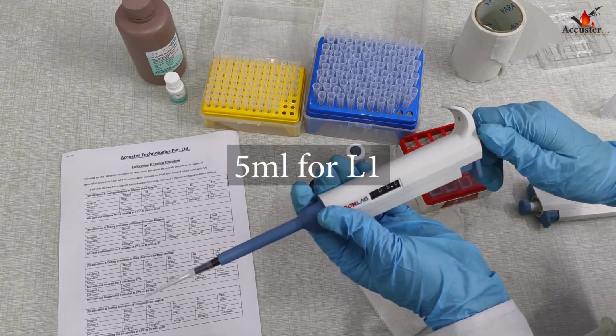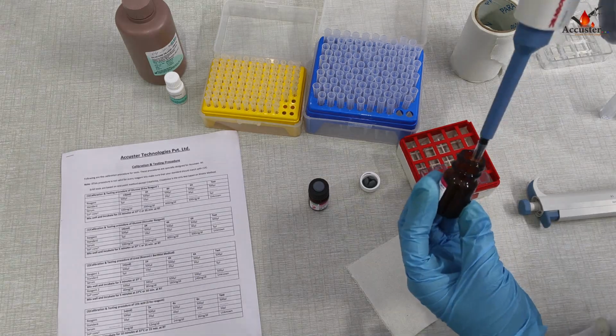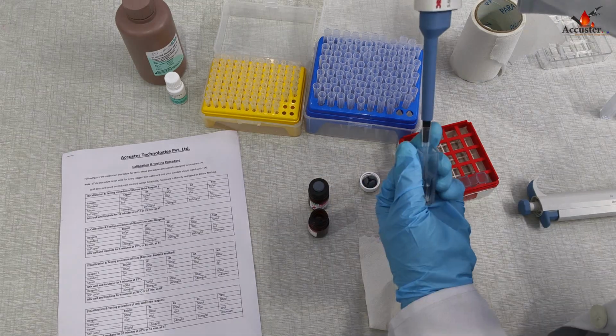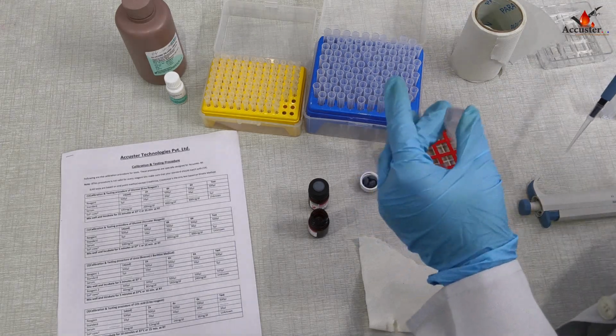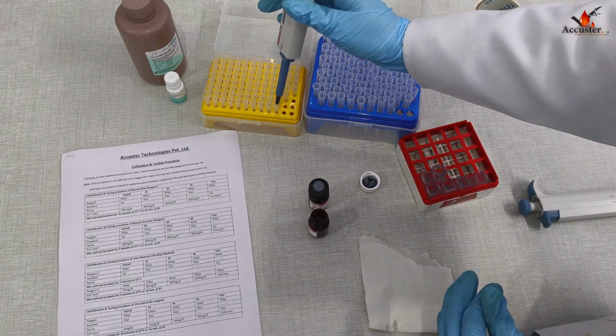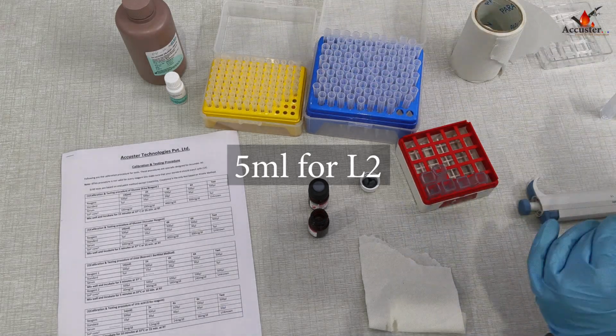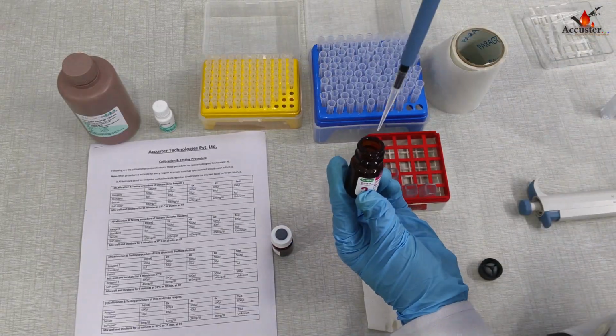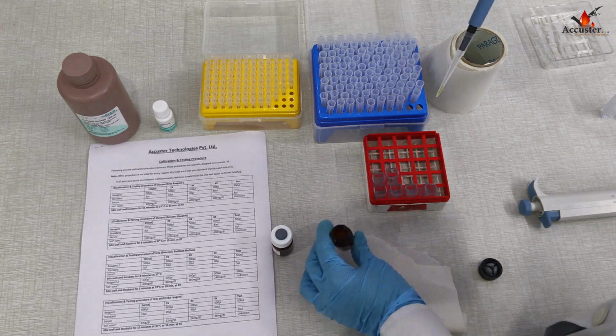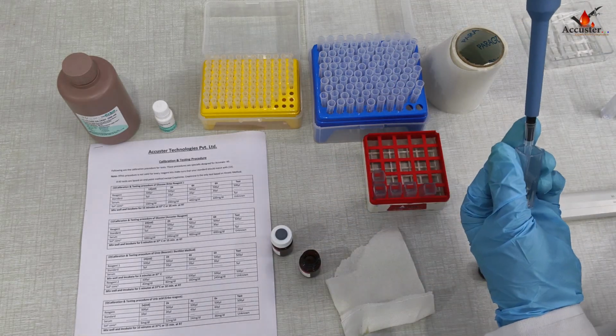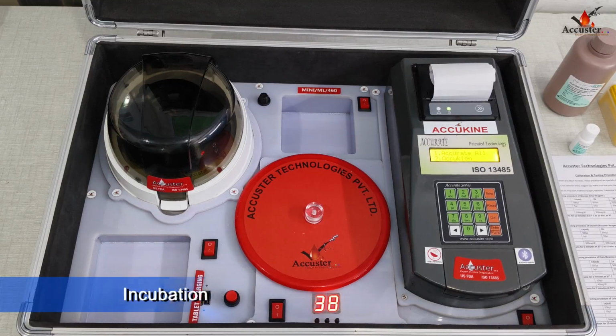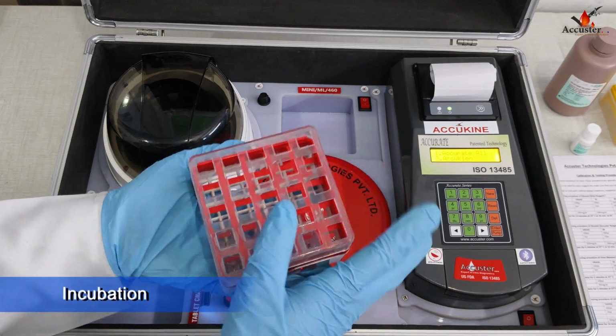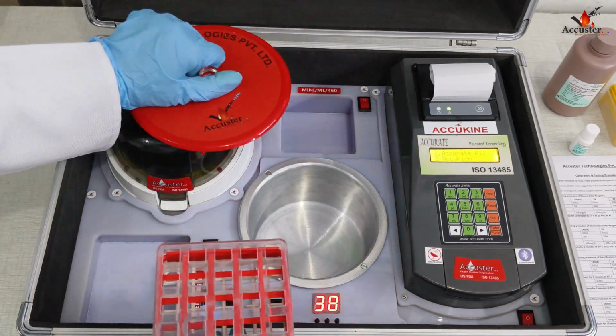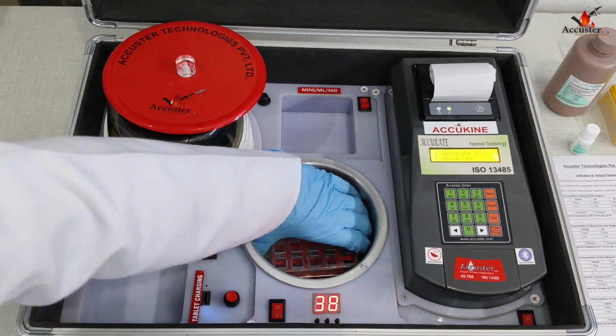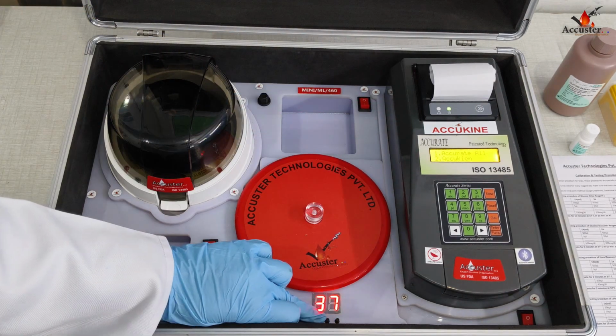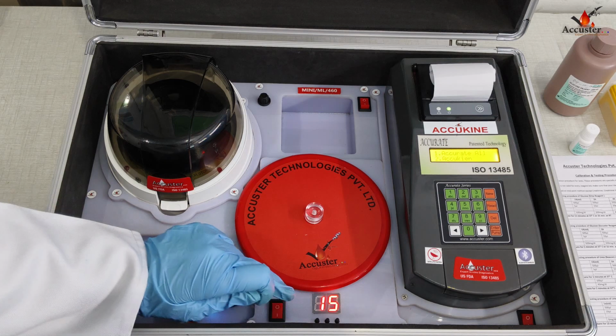Next, 5 microliters of L1 will be poured into the first cuvette of the quality control. And 5 microliters of L2 will be added to the second quality control cuvette. Now we'll do incubation. And for that, calibration and quality control cuvettes are prepared. Next, we will incubate at 37 degrees Celsius for 15 minutes or at room temperature for 25 minutes.